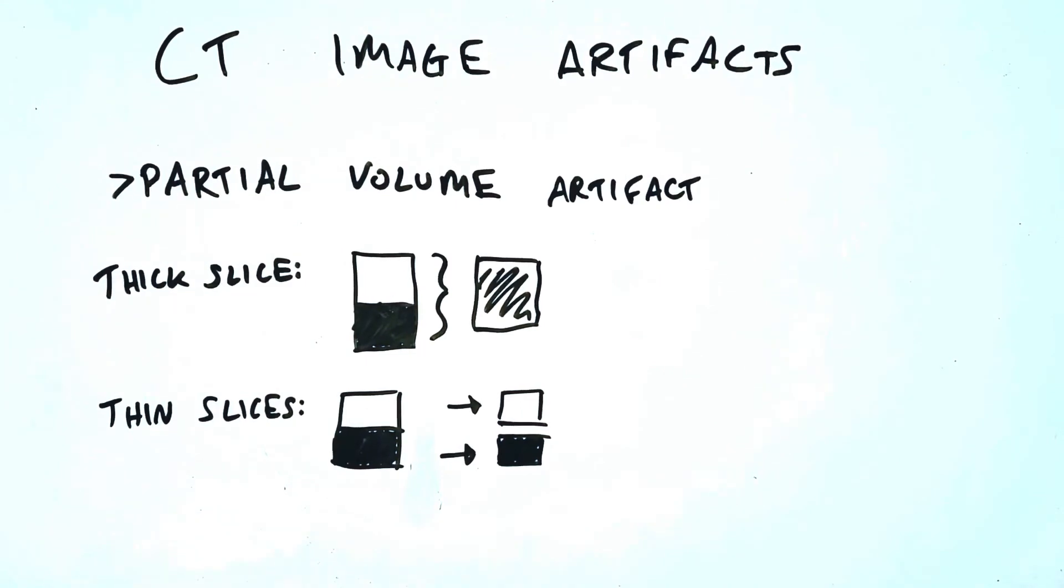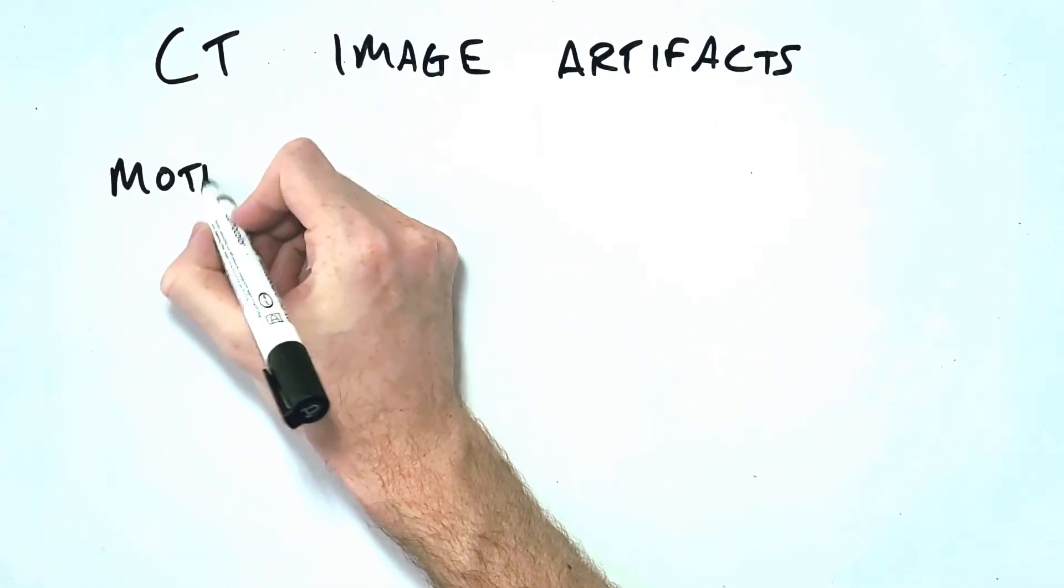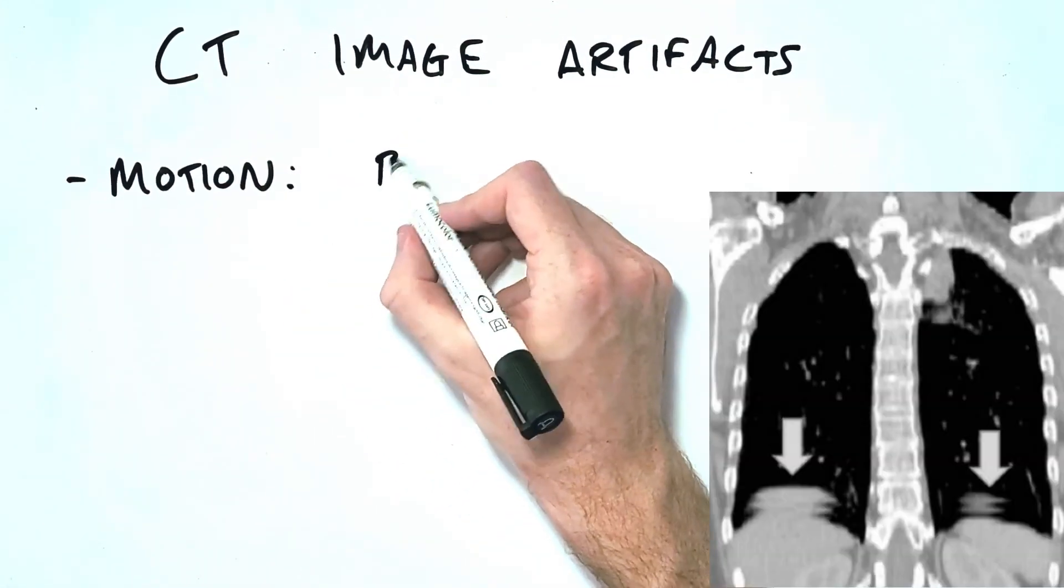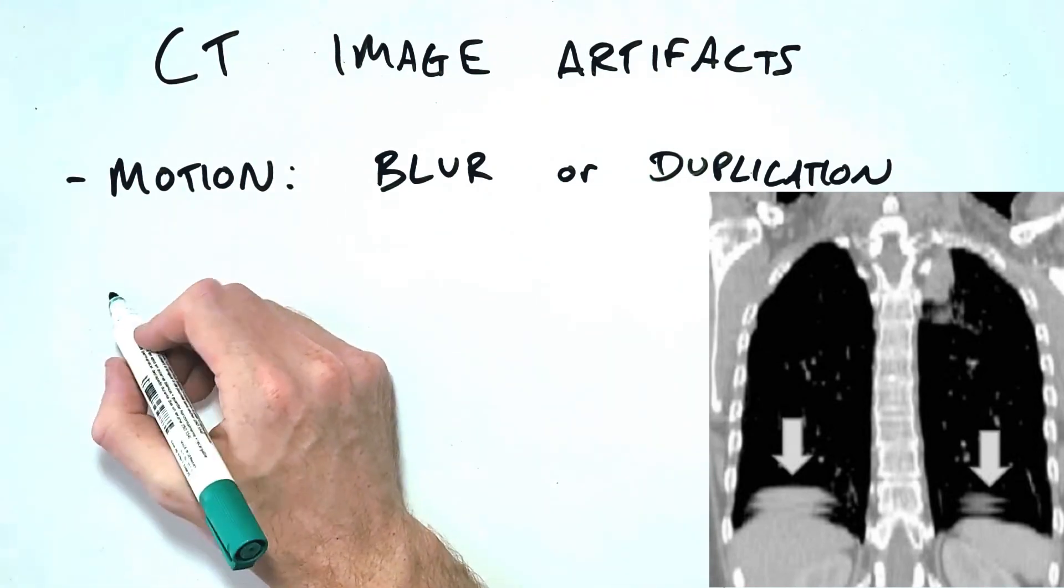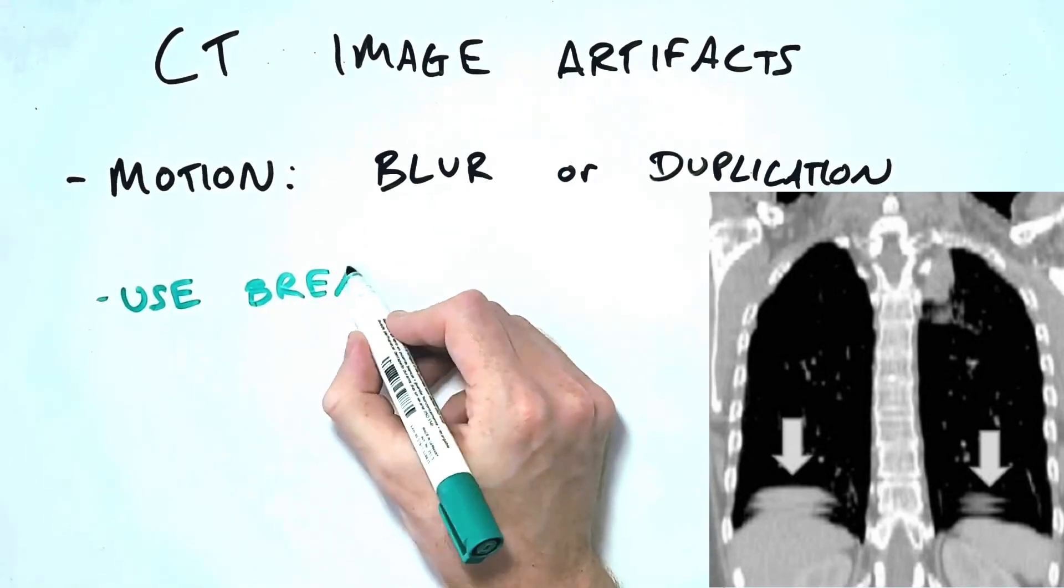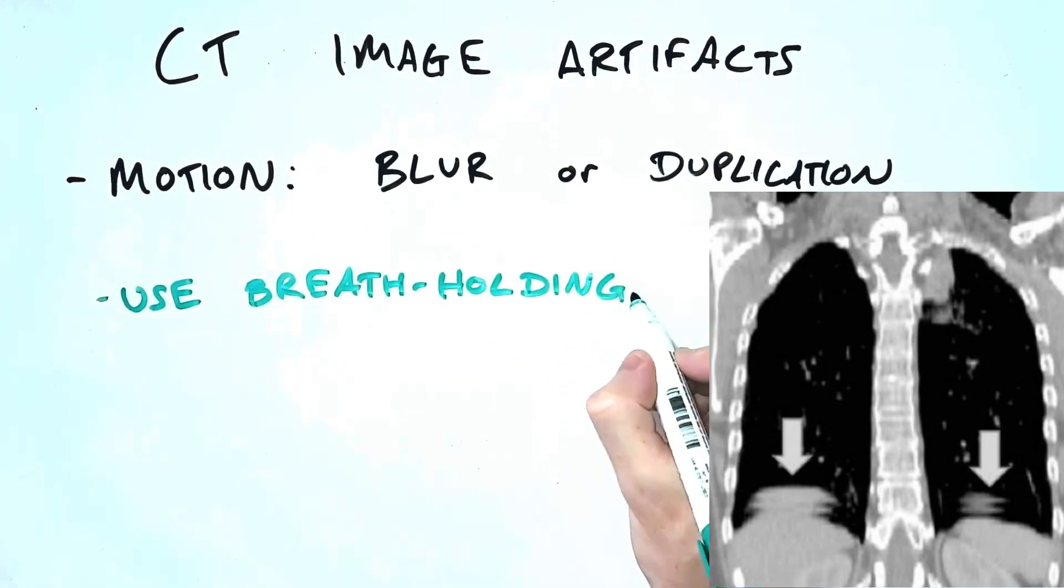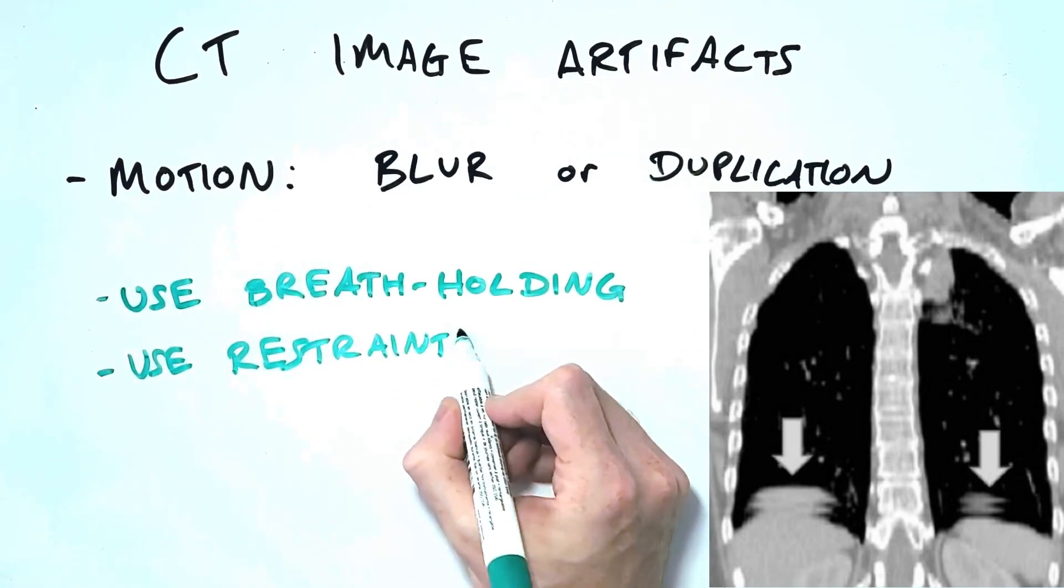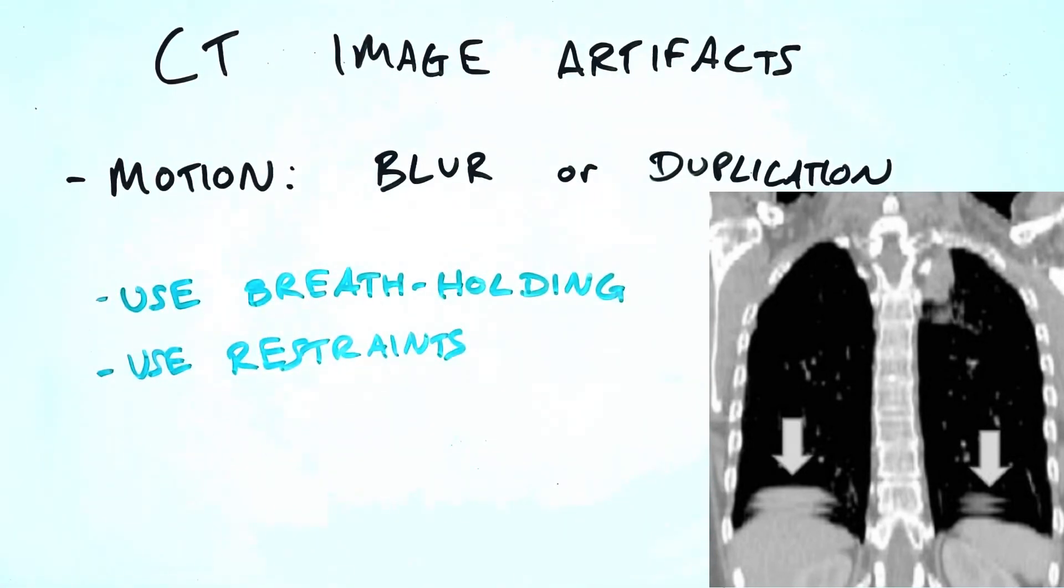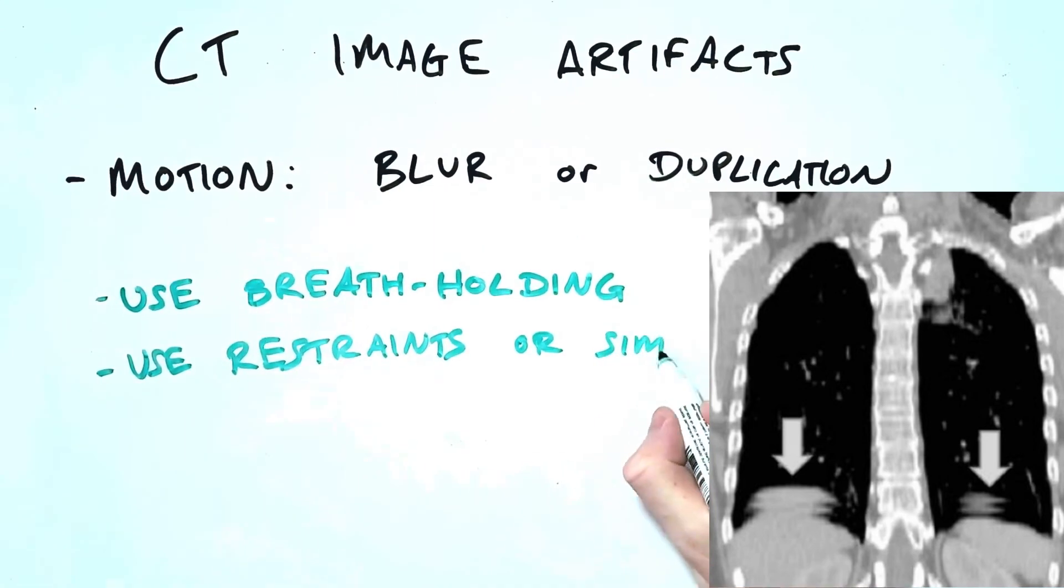Perhaps the easiest artefact to identify is motion and this applies simply as a blur or possibly as the same structure appearing in different positions between slices. The most common example would be motion in the chest due to the patient breathing so the solution is to have the patient hold their breath. If you're working in pediatrics you may need to be more creative with the methods to reduce motion, for example using distraction techniques, restraints or in some cases anaesthesia.